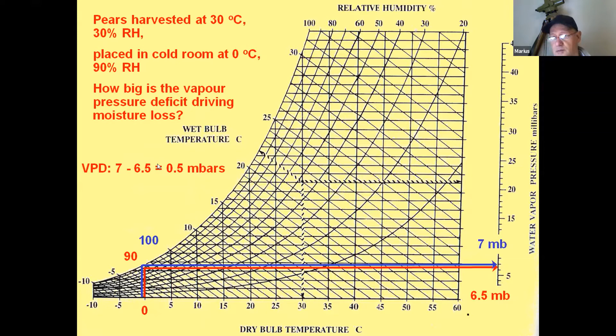Obviously, the fruit will not stay at 30 degrees Celsius because you're in the cold room with air running around at 0. So obviously the fruit's going to cool down. So at the time that the fruit is cold, what is the situation? Cold room is still 0, 90% humidity. It's still 6.5 millibars of vapor pressure in the air in the cold room. The fruit is also now at 0, 100% humidity because it's a fresh fruit, which gives us a vapor pressure of 7 millibars, and that gives us a deficit of only half a millibar. And that's why we cool fruit.